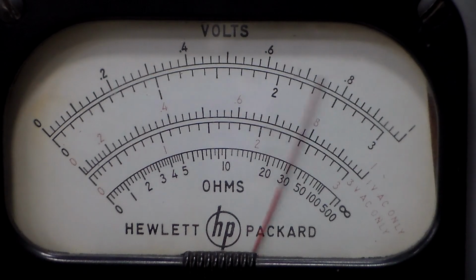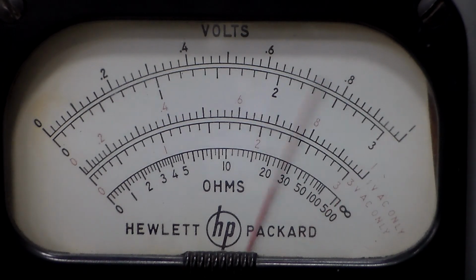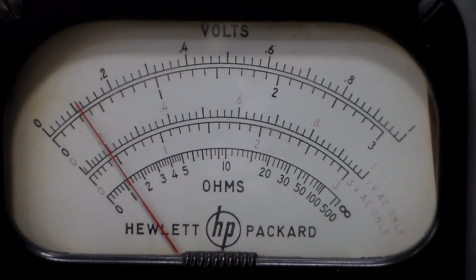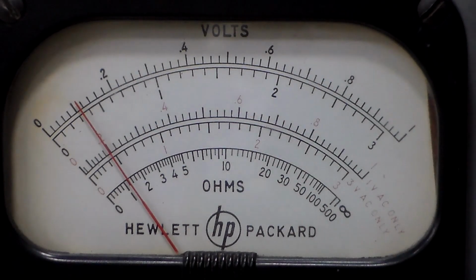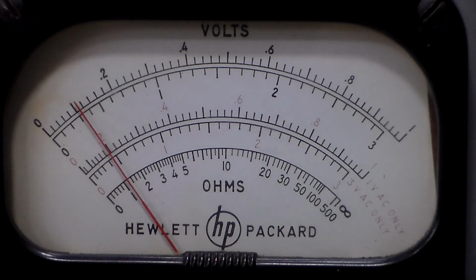If I go to 1 volt, that's reading just a hair under, not even that, but it's close. So we go say 100 millivolts, and that's where most of our error is, and we're talking, it's reading 101 instead of 100. And if you do the quick math on that, that is 1% at that point. It's 1% high. So that's quite good.